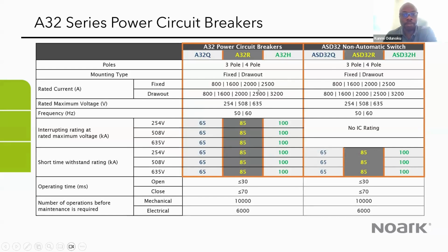The ratings for the A32 go up to 3,200, both for the fixed and the draw out. The maximum voltage is 635 volts. That's the rated voltage, and the nominal voltage is 600 volts. This breaker can work for both 50 hertz and 60 hertz frequency. And like I said earlier on, we have the interrupting capacity. We have 3 different families here: the 65 kA, the 85 kA, and the 100 kA.